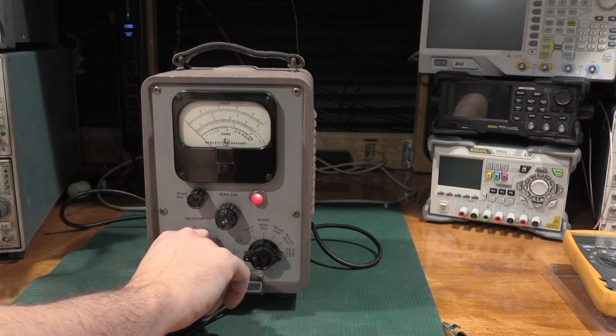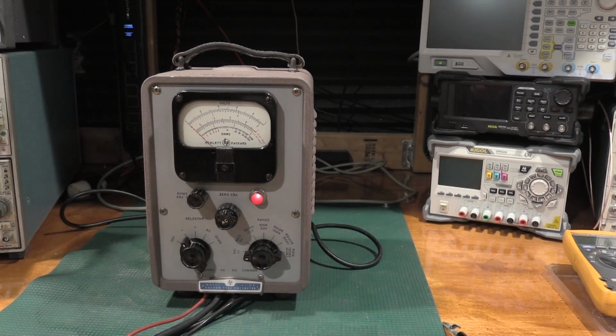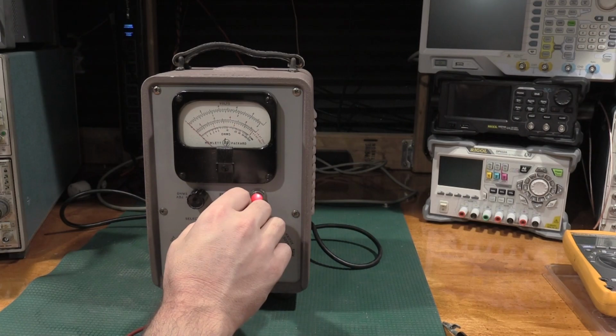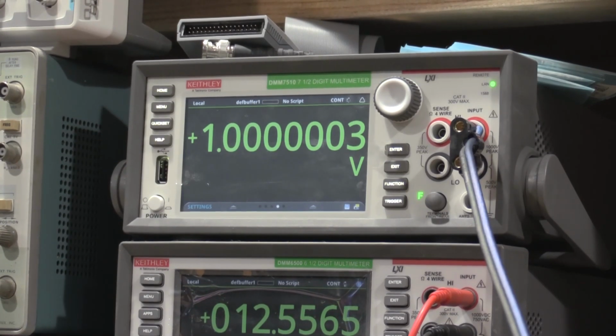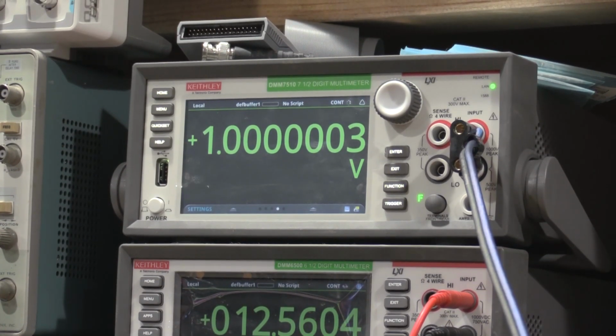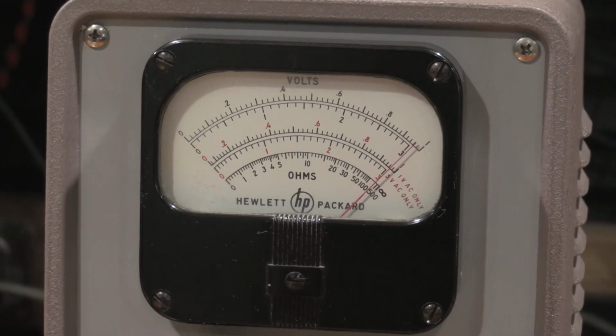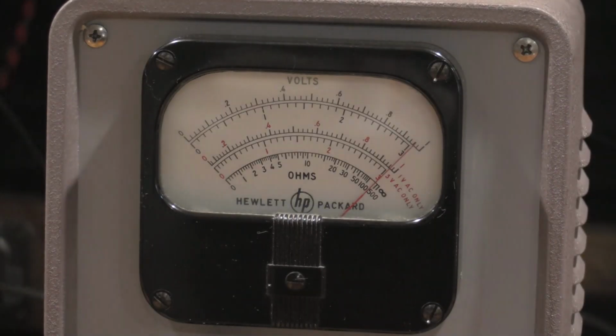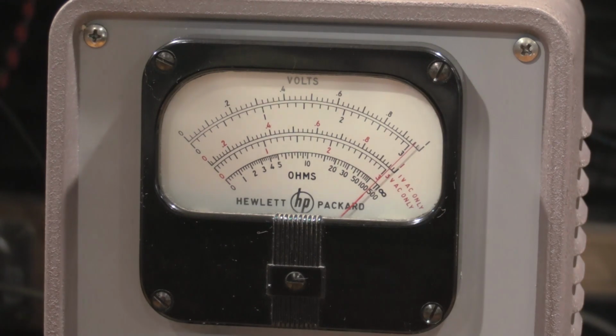If we kick this to negative, we shouldn't see much deflection on the meter, and we don't. That should be enough 1 volts to calibrate the 410B. So we'll move that signal down to the 410 and get it adjusted. Not too bad, but we're off by a touch.